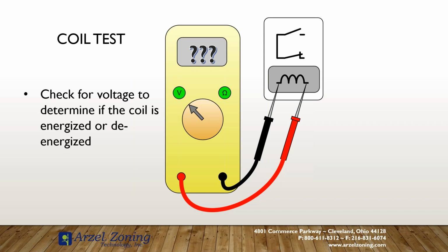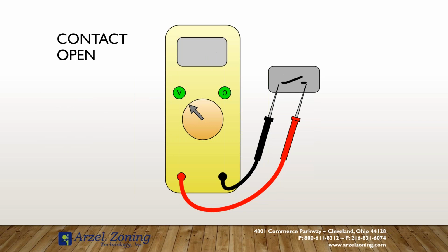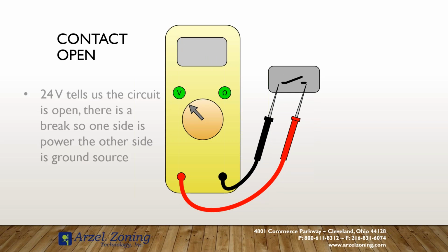And when I know it's energized, I know that those terminals are going to test differently. So if I have that single pole double throw, or I have that double pole double throw, my common source is going to be labeled. And then from the normally open side, if I'm energized, I'm going to read 0. And we'll see that right here. So if I have an open contact, I'm going to read 24 volts. And the reason I read 24 volts on the switch side, if I have an open contact, is because it's broken. One of those acts as the path to ground. The other one acts as my hot source. So if my switch is open, I'm going to read 24 volts across it.